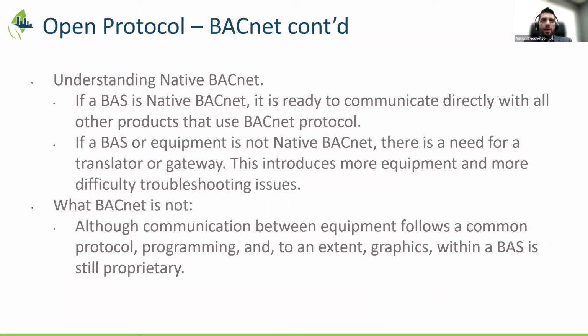When the device is a gateway, I want to stress again there's nothing wrong with a gateway, and most of the time those gateways are BTL listed themselves, which is a good thing. Where problems start to happen is more with how that gateway has been set up or programmed, in the sense that the object names are often the issue. We run into scenarios where you discover a controller and the object names are just something like AI5, as opposed to 'supply air temperature,' which we could understand a lot easier through an English descriptor.